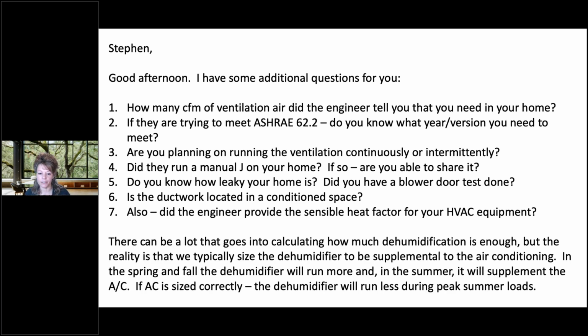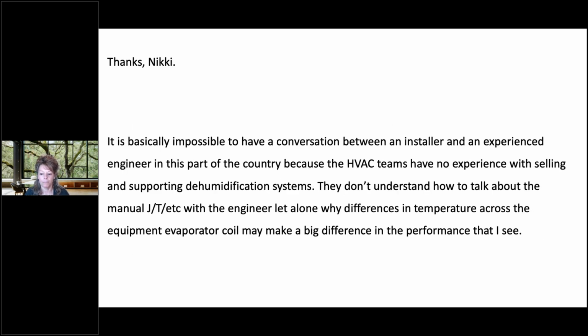So I went on to explain that there's a lot that can go into dehumidification. The reality is, most of the time we are so conservative in our recommendation per square footage that it should cover it. 99% of the time it covers, because we are so conservative. We would rather have the dehumidifier oversized than undersized. His response back was basically that it's really hard to have a conversation between the HVAC installer and the engineer, and a lot of them just don't understand these dehumidification systems, which we are seeing.